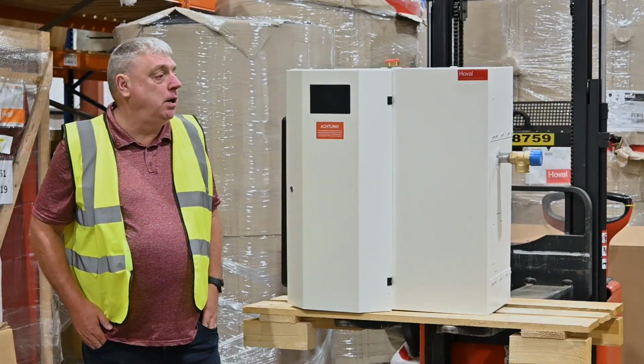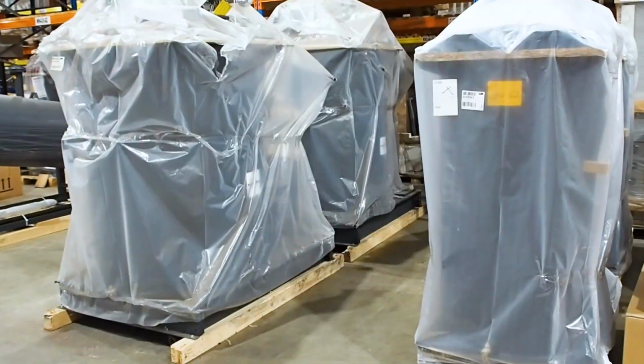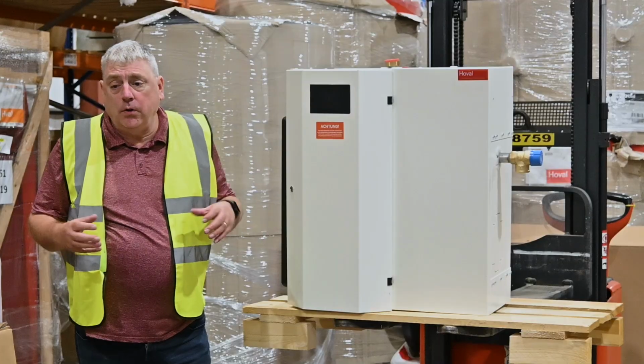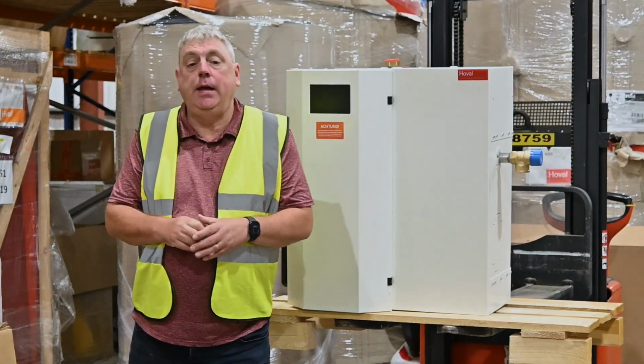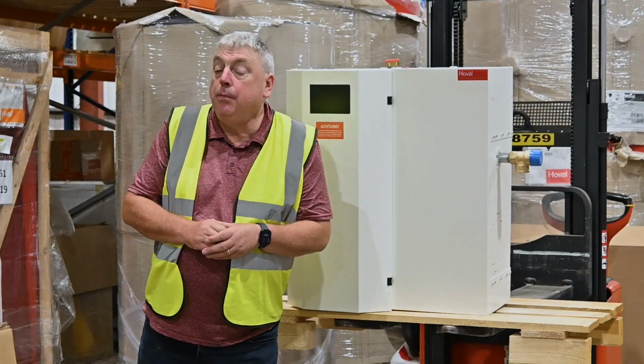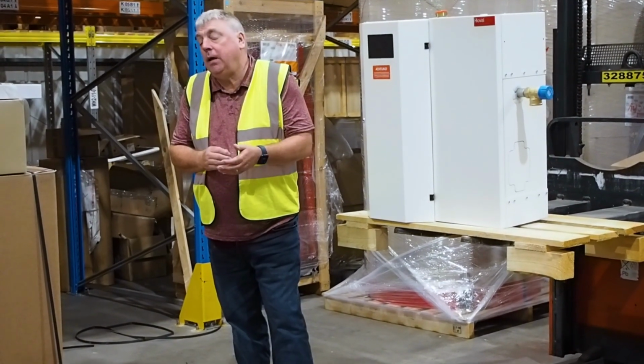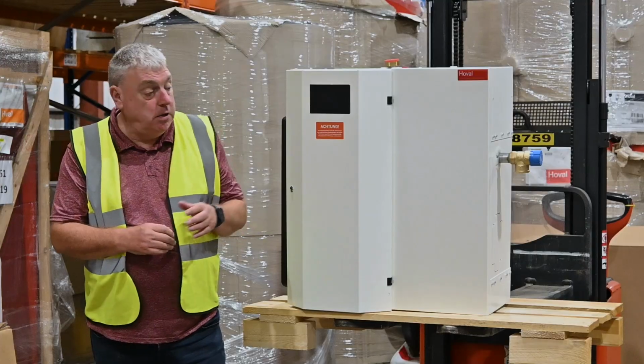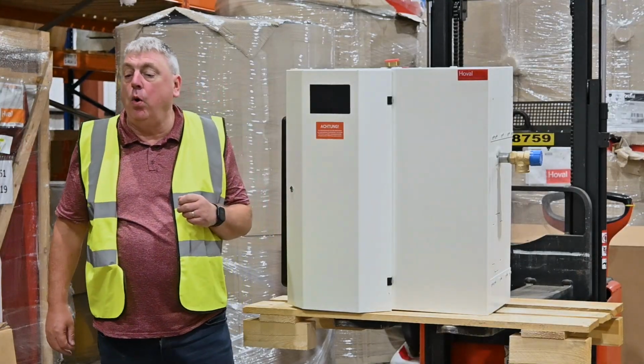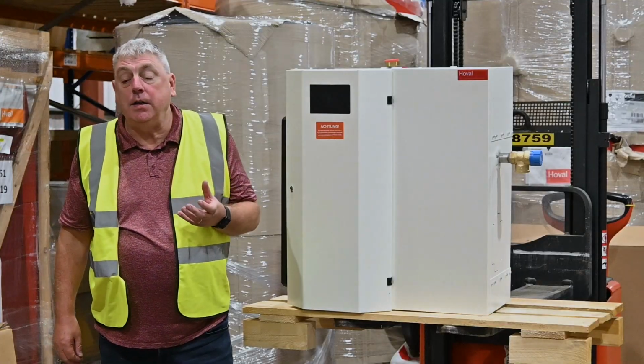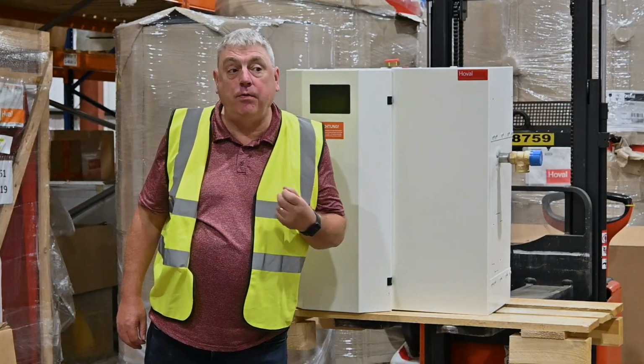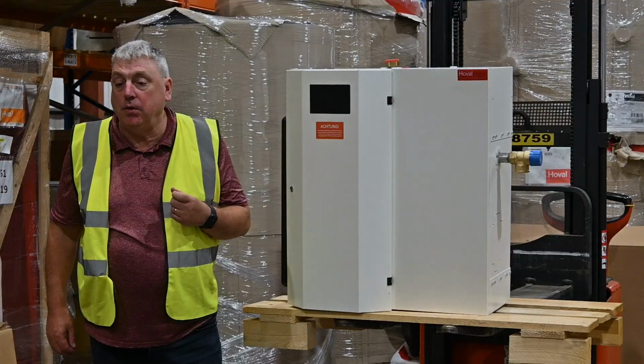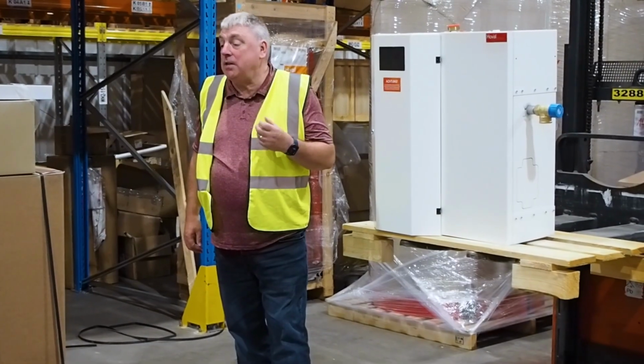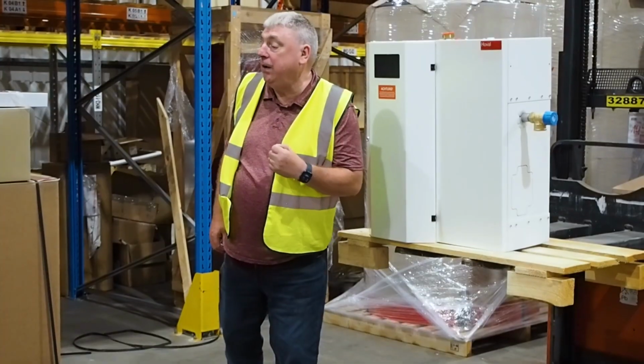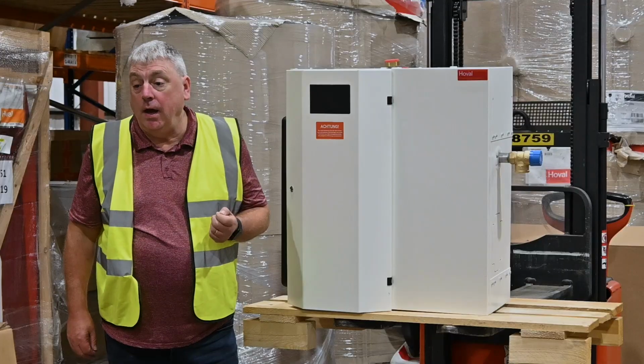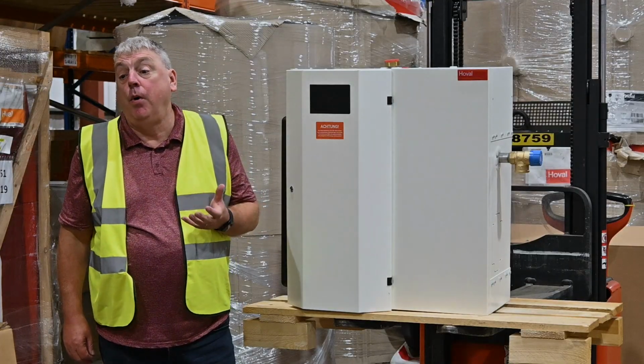Conventionally, if you're using a boiler or boilers like the ones over there to make domestic hot water, there's no real effort to control heating supply temperatures. You simply take heating water from the boiler, typically at 70 to 80 degrees C, to the device that you're going to make the sanitary hot water in, and the focus in those devices is to make sure you've always got enough hot water for your needs at the right sort of temperature. The heating return temperature back to the boiler or the heat generator isn't really considered, and often it can be 60 degrees C or more.